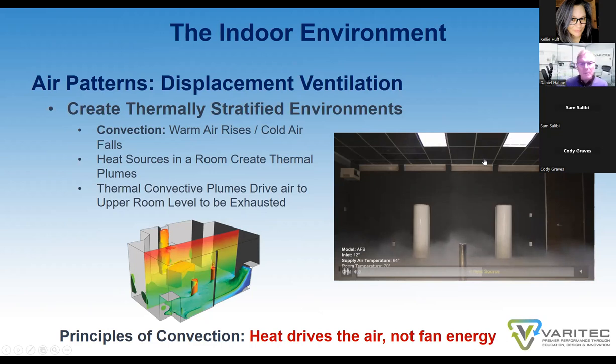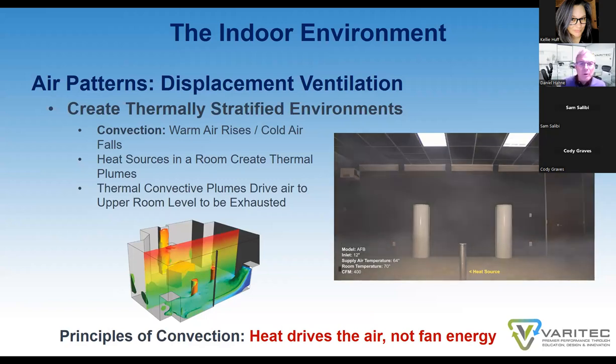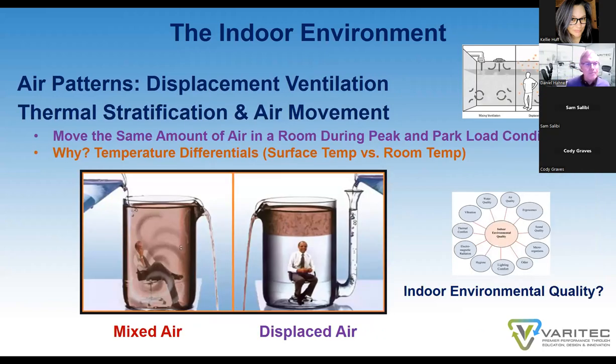Well, the convective plume of a human occupant, hopefully with a body temperature of 98 degrees, is roughly 30 feet per minute. 30 feet per minute of air continually moving upward, drawing clean conditioned air across the breathing zone. Consequently, displacement ventilation offers improved indoor air quality, and ASHRAE standard 62.1 assigns displacement ventilation a 1.2 ventilation effectiveness rating, which allows buildings using this design to design for 20% less outside air.